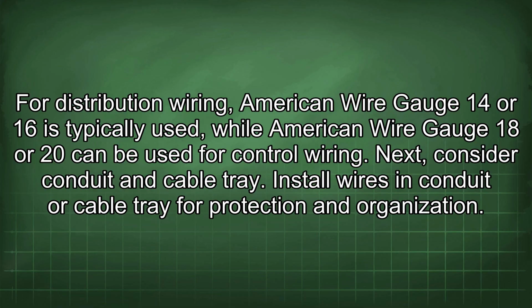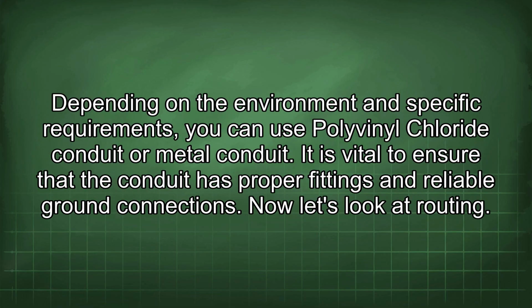Next, consider conduit and cable tray. Install wires in conduit or cable tray for protection and organization. Depending on the environment and specific requirements, you can use polyvinyl chloride conduit or metal conduit. It is vital to ensure that the conduit has proper fittings and reliable ground connections.